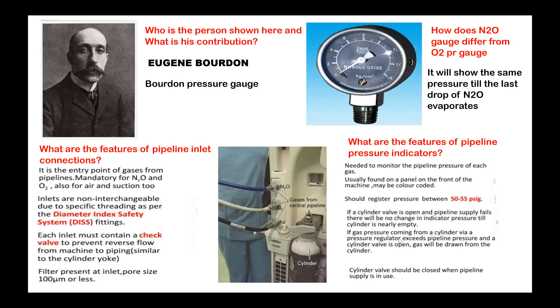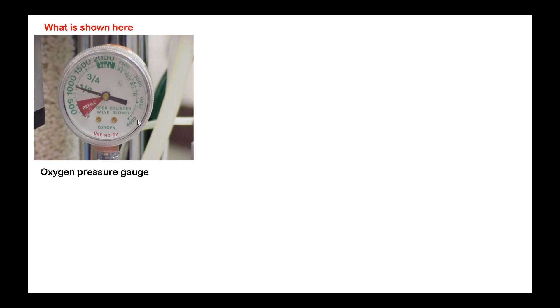Okay. And these are all the entry points for machines from the outside where you use the diameter index safety system. Right. Pipeline pressure indicators are very important for telling the reduced pressure. This is the oxygen pressure gauge. So here it is showing all the features. The pressure is given both in pounds per square inch as well as in kilograms per centimeter square, and it is staying full when the new cylinder is fitted. The needle should point here, and when it starts dropping, it is showing the zone to refill. These are all safety features that are sometimes asked in the examination.